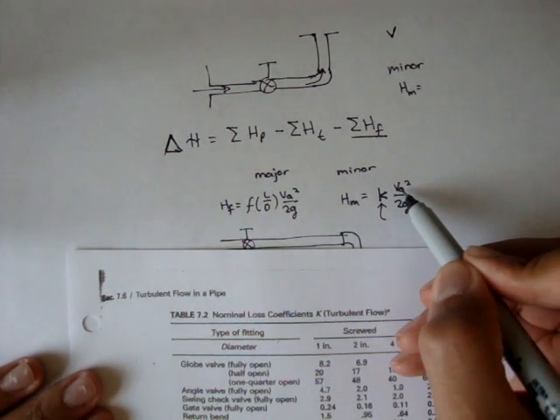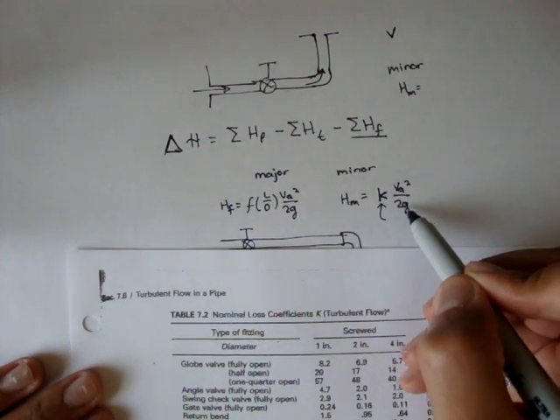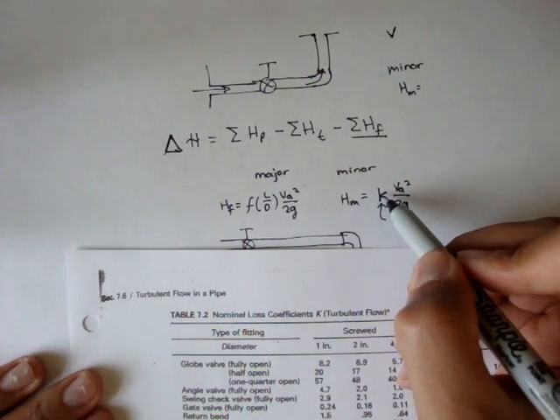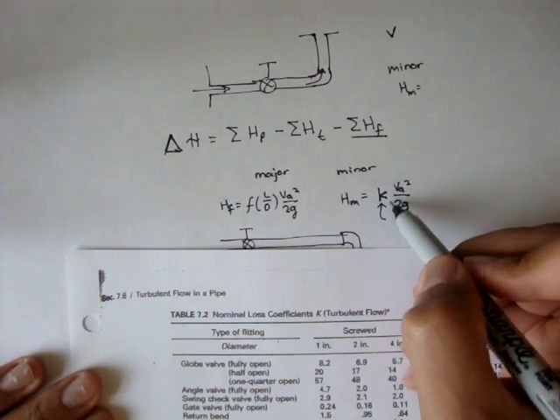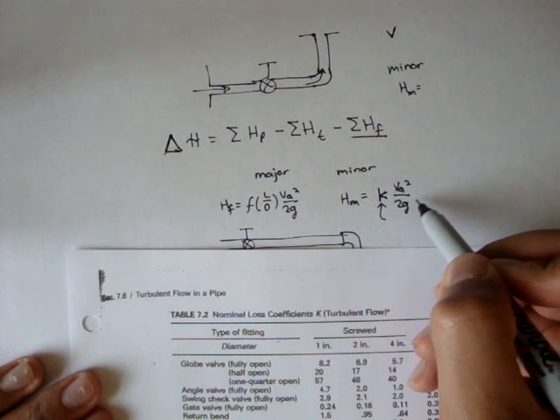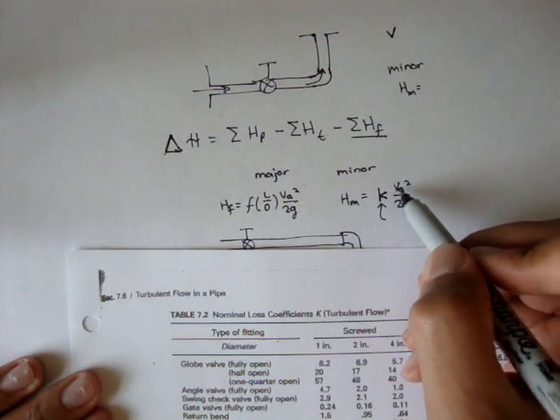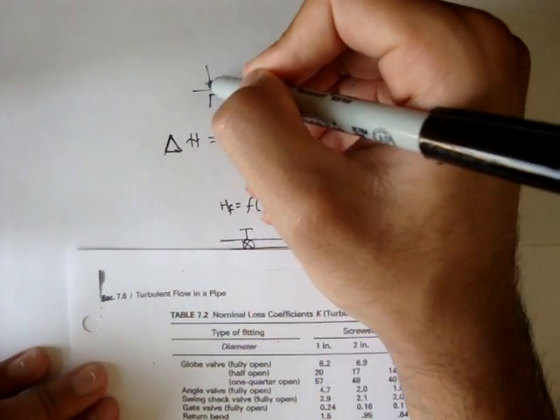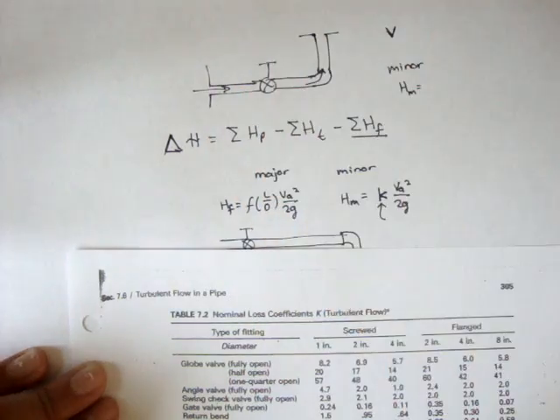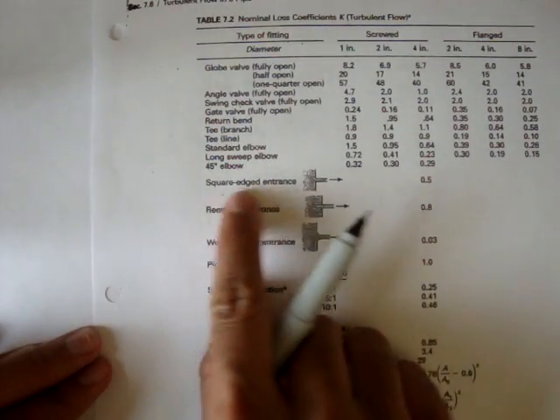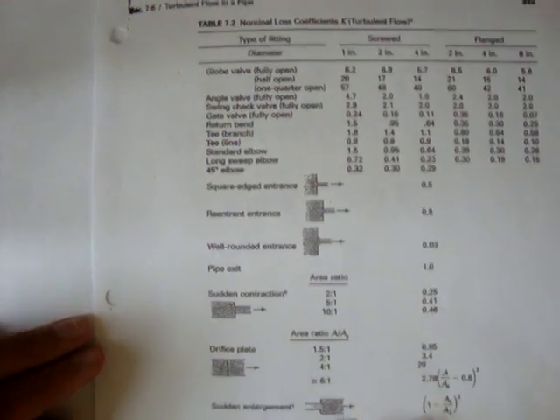Now, since VA squared over 2G remains constant, we can just sum up all the K values and multiply it by the VA squared over 2G. Remember, VA is just the average velocity, and in this case, it's just V. So, we had an entrance loss, and it looks like it's just a square-edged entrance. On my chart here, I see that the square-edged entrance has a K value of 0.5.